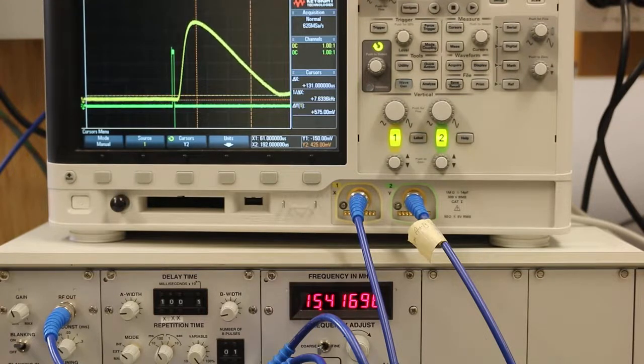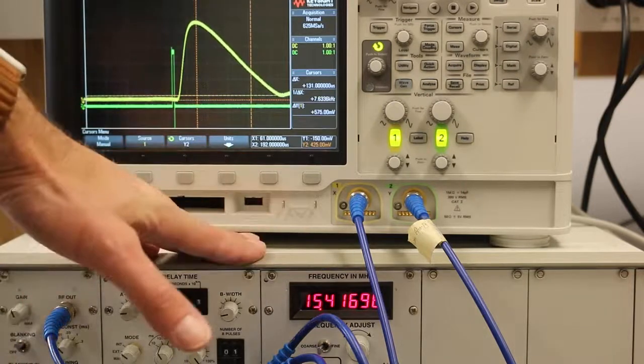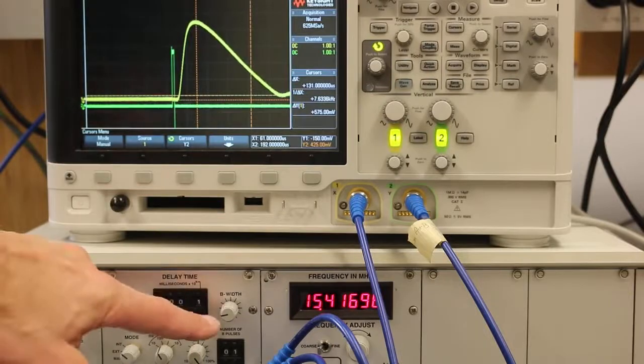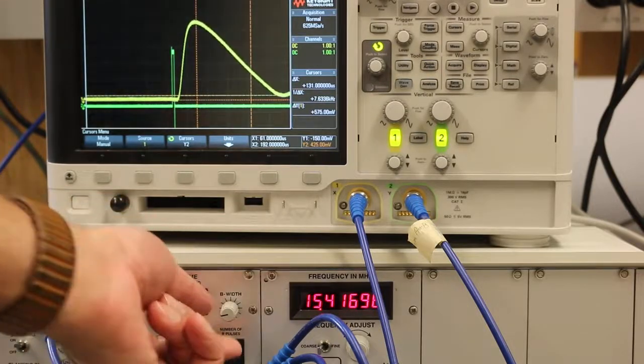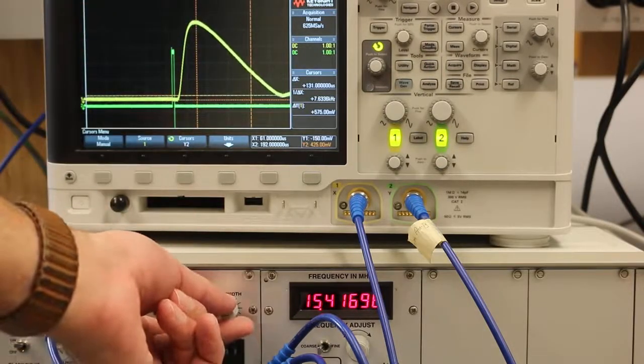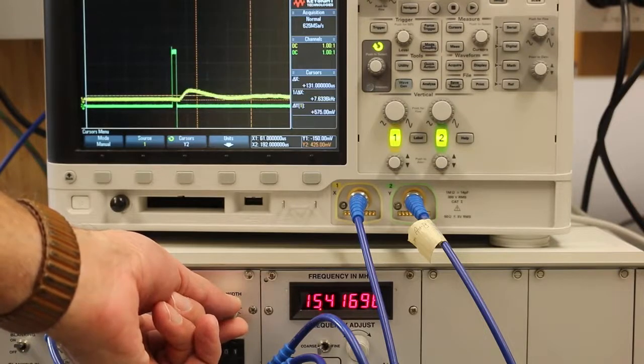But remember, for T2, which is what we're measuring this signal, we want the A pulse to be 90 degrees, we want the B pulse to be 180 degrees. So on the B pulse, relative to this timing, I'm just going to keep increasing it until this signal gets minimal, not maximum. And that's my indicator that B is at 180 degrees, because I'm rotating it through the plane of the detector all the way, inverting it to the negative Z-axis. So it's exactly opposite to the equilibrium of where the spins would be in the static magnetic field. And because they're not aligned at all with the axis of the detector, I get a minimal signal.